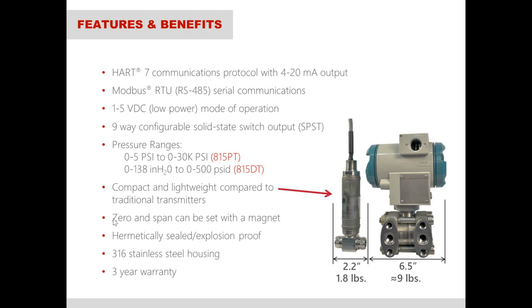This is especially valuable to some customers that have equipment out in the field that uses 1 to 5 volt DC, and then some of their equipment uses 4 to 20 milliamp. And it prevents them from having to stock multiple different model numbers when they can order the exact same model number and just set it up how they want it in the field.